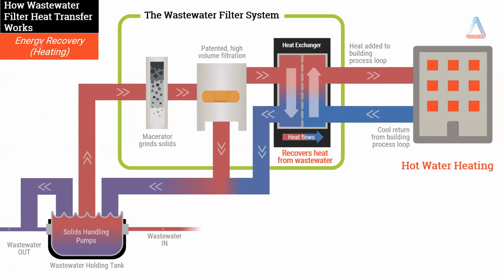So this slide here shows energy recovery, and I hope everyone will bear with me as we show the color coding for warm and cold, just to really show how that energy transfer works. So in the concept where we're looking at energy recovery, the return line, or the line moving into the heat exchanger on the load side, so what we would typically look at as the building or the geothermal, will come in at a cooler temperature than the wastewater.